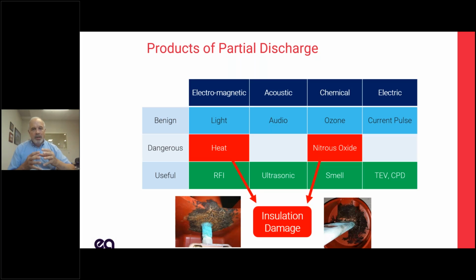So this is why surface discharge happens at a faster rate. You've got heat and nitrous oxide that are affecting the insulation. Internal discharge, you really only have the heat, so they move slower. It's all kind of logical. Now, the nice thing, the useful fact is the smell. You can smell ozone. It gives you an indication something might be going on.